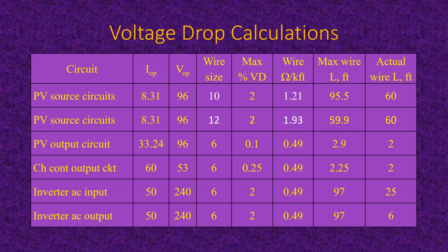If you're doing a utility scale system, you're probably going to be operating at 1500 or about 1200 volts. So your voltage drop is only going to be 1/10 as much as it is for these circuits here. Or the other way of looking at it is you can go 10 times as far with the same voltage drop if you increase the voltage by a factor of 10, which is now happening behind the fence in utility type arrays. Residential limited to 600 volts, commercial 1000 volts. And if you're behind the fence on utility, you might be going 1500.